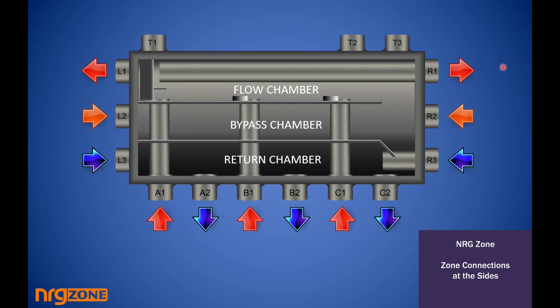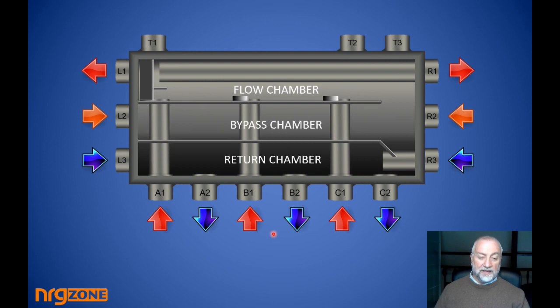So it's completely up to ourselves again, but now we have heat introduced at A1, B1 and C1 from 3 respective boilers, and returns typically would go back from A2, B2 and C2. If that is the case, your zones are then taken from L1 and L2, or R1, sorry, being your flows, and L3 and R3 being your returns in conventional piping.